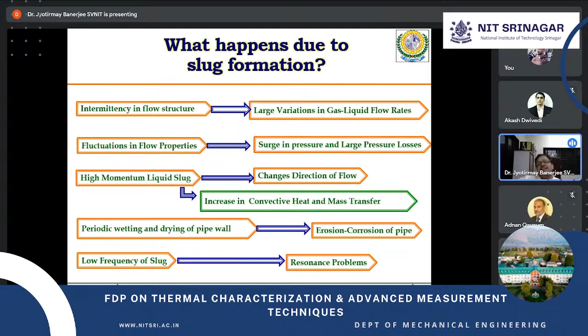These are catastrophic failures we captured, available in literature. In Canada, there is a group working from a chemical background looking into this erosion corrosion. At some point we utilized some of that data to develop an erosion corrosion regime map and supplied it to GIPCL, so they know which regime to operate in to avoid erosion and corrosion in the long run.